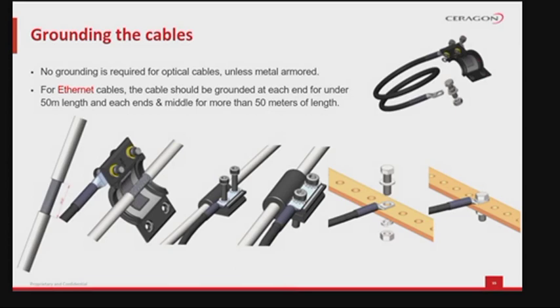In the case of the IP20C, there is no RF cable to be grounded, only optical and electrical Ethernet cables are involved. Remember that the optical cable does not need grounding as it does not conduct electricity in most cases, unless it involves a metal armor. Ethernet cables are grounded with the use of a special grounding kit. These grounding kits may vary with vendor or client, but they are similar in process.